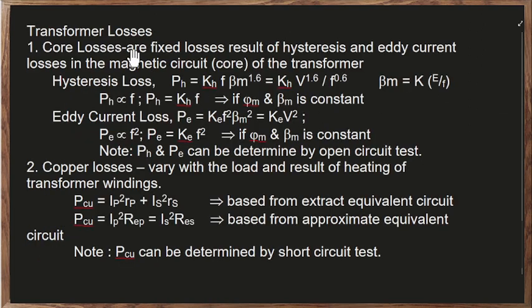Then transformer losses. What are the different losses in a transformer? So we have core losses. These are fixed, the result of hysteresis and eddy current losses in the magnetic field or core of the transformer. So they are fixed, no? If you have the same type of core, the same material of the core, your eddy current and hysteresis loss is the same, no? So the formula for hysteresis loss is this one, no?